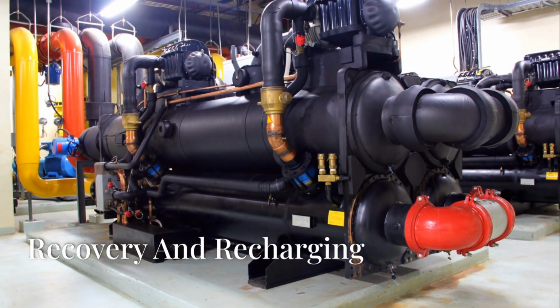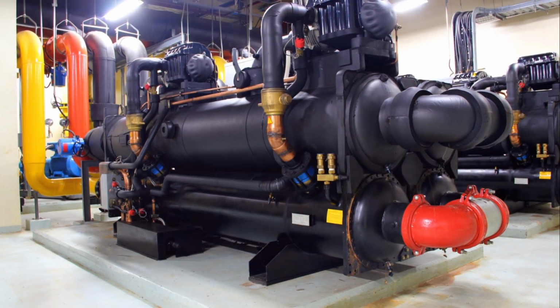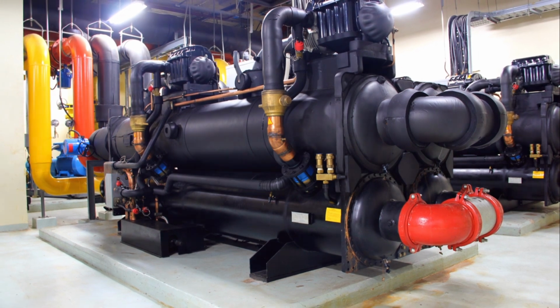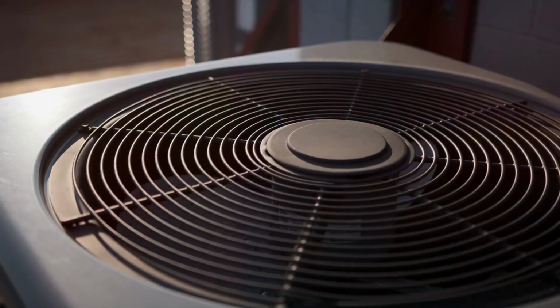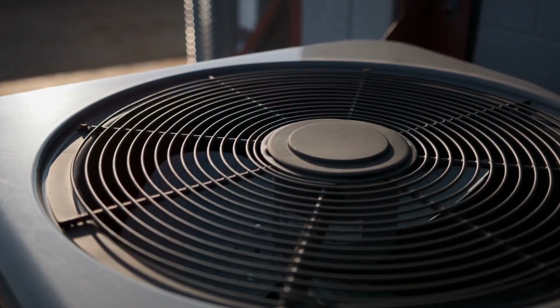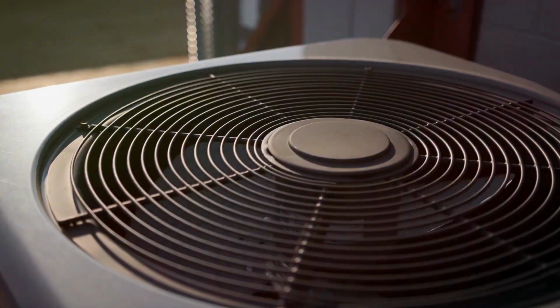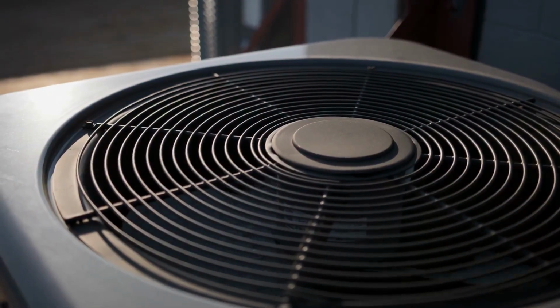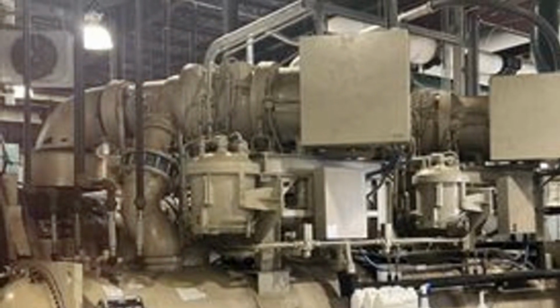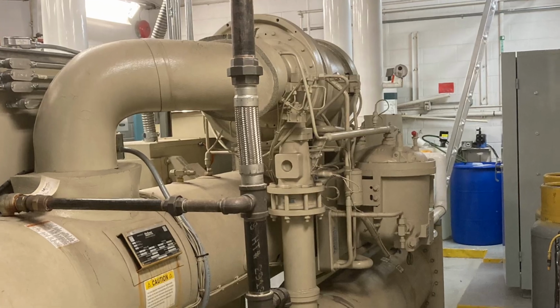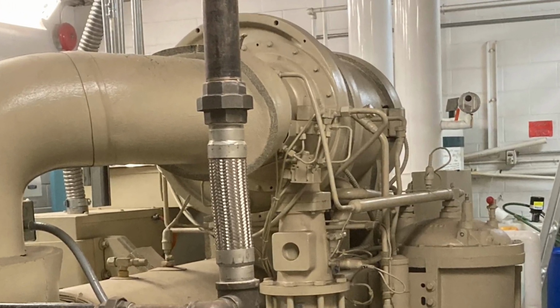The process of recovering and recharging hundreds or even thousands of pounds of refrigerant in and out of a chiller is quite a bit different than the process of recovering and recharging a small AC unit. At some point in your career you will likely need to recover refrigerant, make repairs, and recharge large chillers with hundreds or even thousands of pounds of refrigerant.